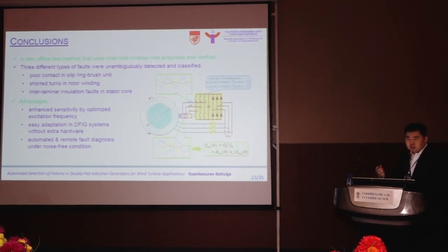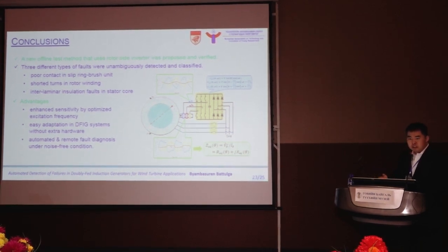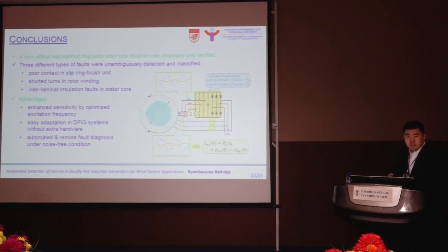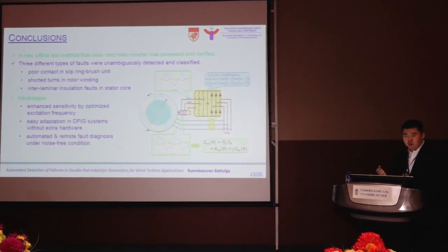So during the standby, when the DFIG is not working, the inverter can inject signal to the rotor, and then that pulsating field will be created, and from that we can measure the voltage and currents by using the already existing measurement instruments in the DFIG system, like CTs or voltage meters.